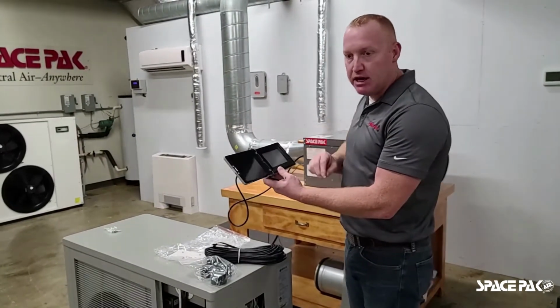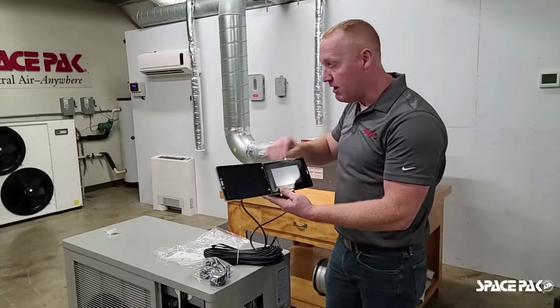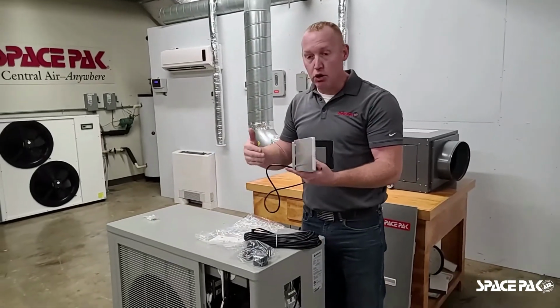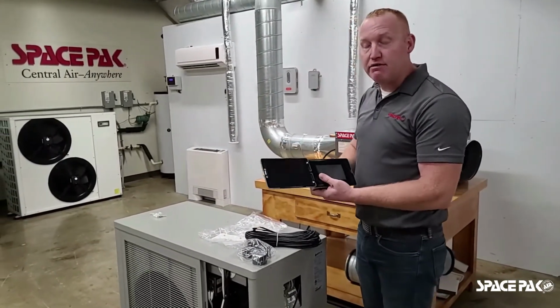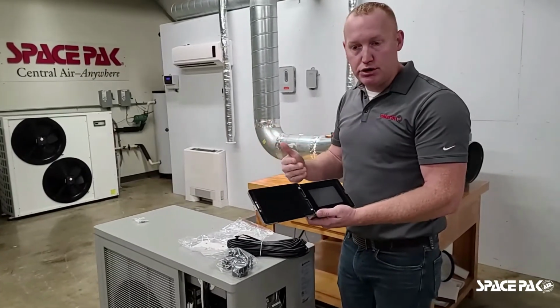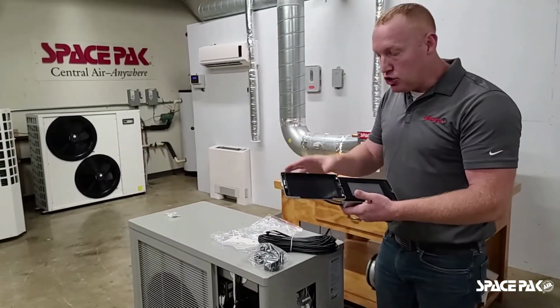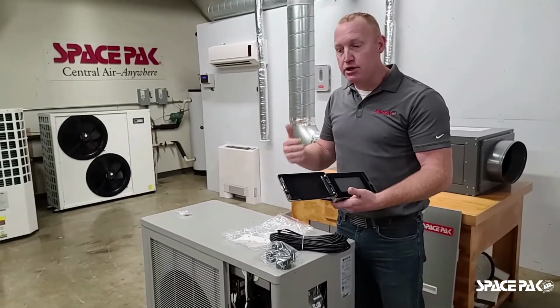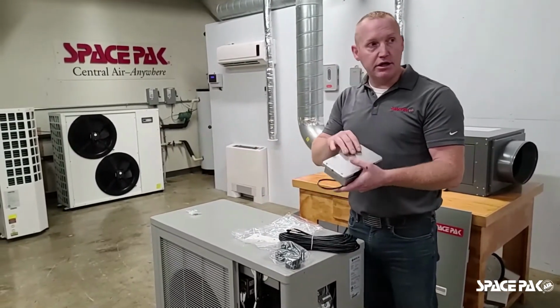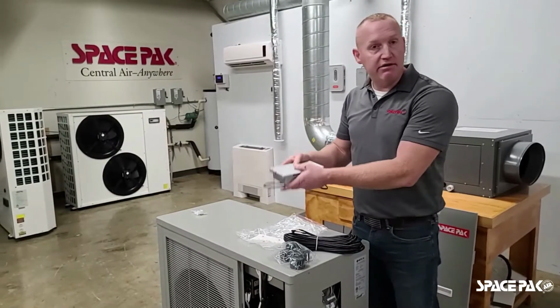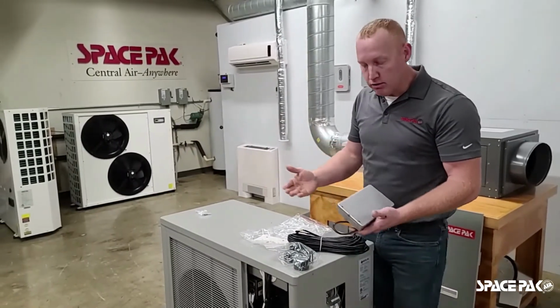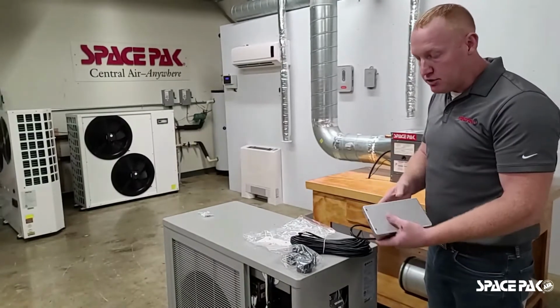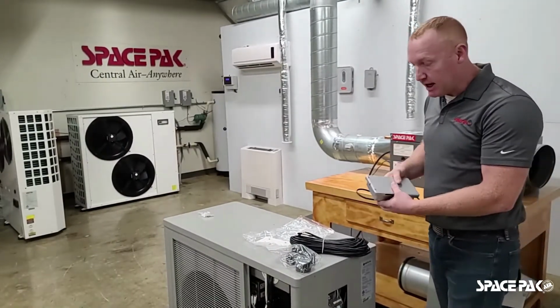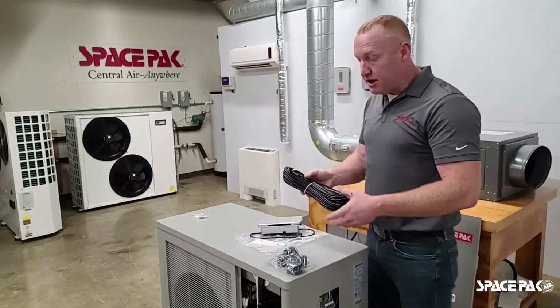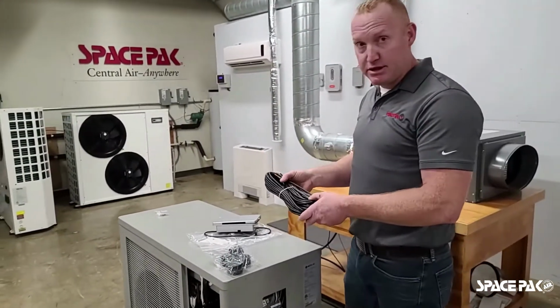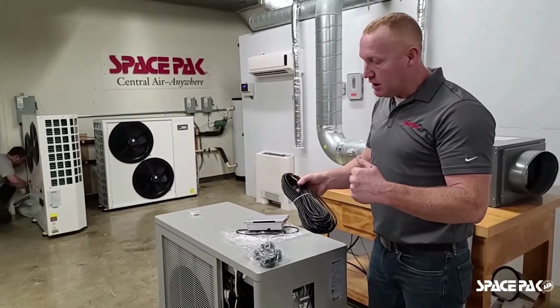Any of the adjustments made are not saved in this unit here. They are actually saved in the main control board. So for instance, even if installation or some need requires it, you can make all of the settings and changes that you need in your unit and basically unplug this unit and not even have it connected to the unit while the unit is running. So this can be used either outside or permanently mounted inside. Now, it comes shipped standard with approximately 65 feet, might be 64 or 66 feet, of control wire.